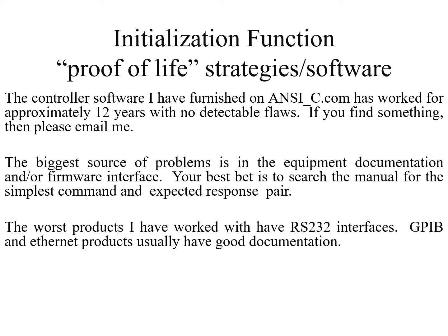The biggest source of problems are actually in the equipment documentation and/or the equipment's firmware interface. Your best bet is to find the simplest possible message you send to it, like hello, how you doing, and then a response comes back. You want to have the simplest one that you can find. Don't try to launch right into something big. Look for the simplest one. It doesn't matter what it is, as long as your equipment is not damaged or doesn't do something stupid like screw up some calibration. You want to find the simplest phrase that you send to it. You have to look through the equipment documentation.